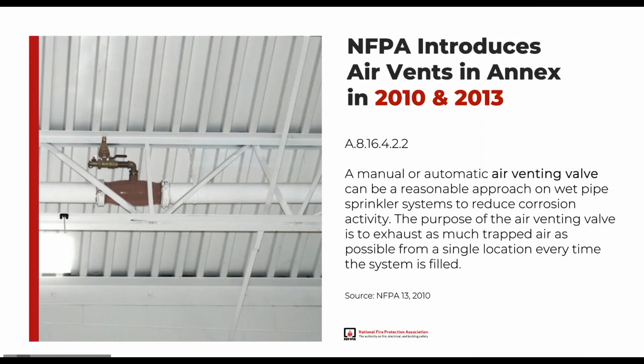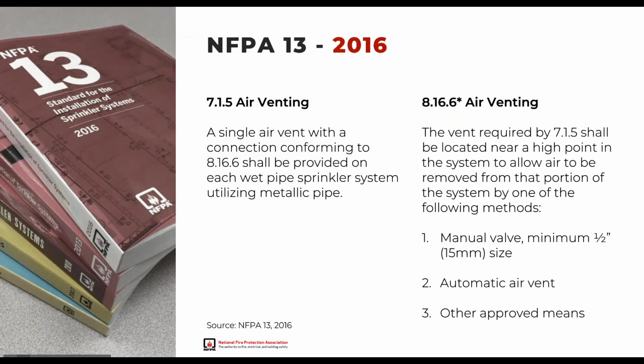And then from the 2007 language, they first made mention in 2010 and then repeated again in 2013, the idea that you have some type of air venting protocol on your system. And in 2010 is when they introduced the suggested language that you have a manual or automatic air vent to reduce the amount of air in a wet sprinkler system. Well, as we all know, it takes many, many years to get into a code cycle, probably 10 years from when language is suggested. So what was recommended in 2007 and then suggested in 2010 and 13 became mandated in 2016, again, almost 10 years later.